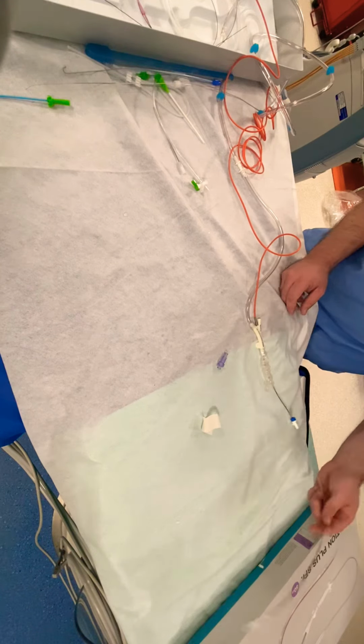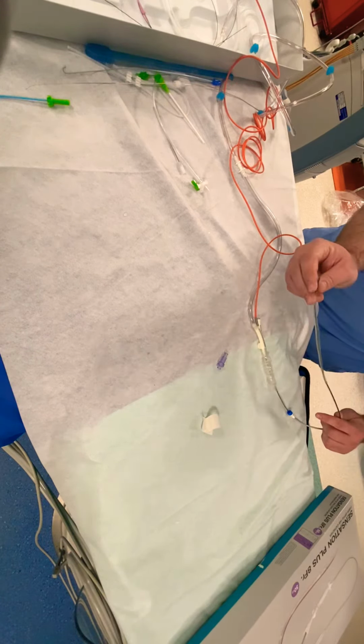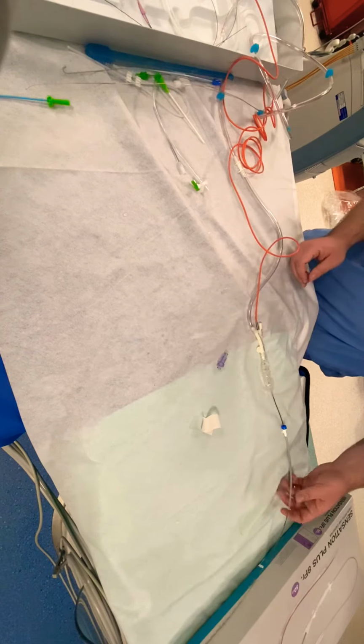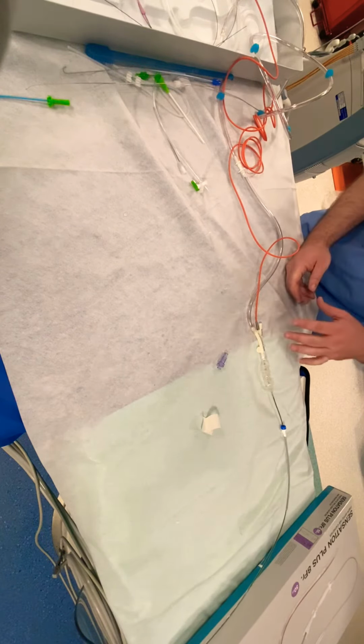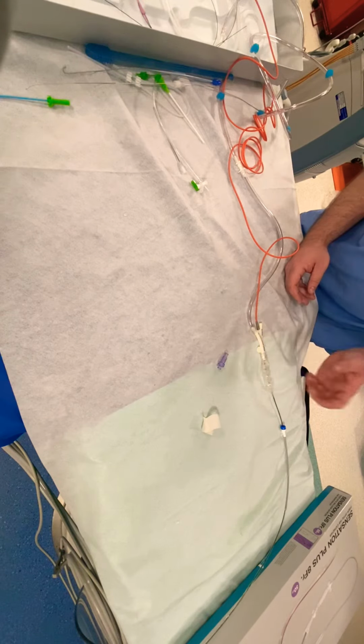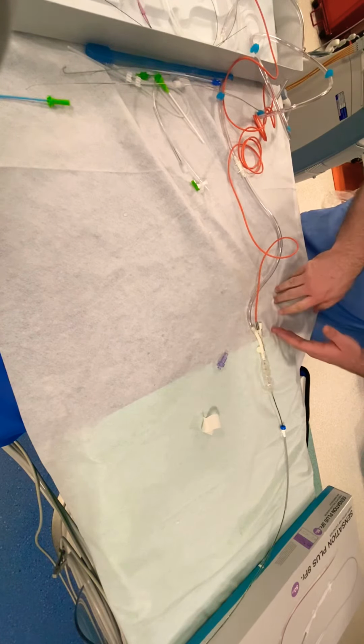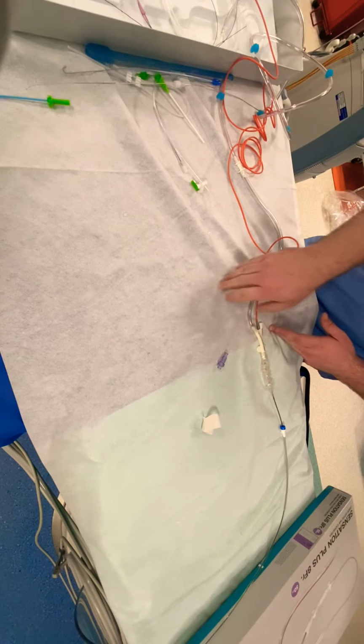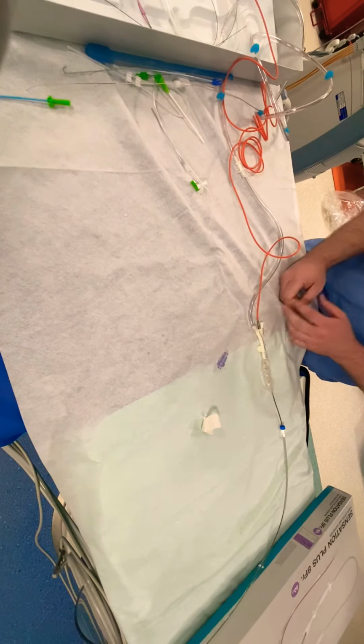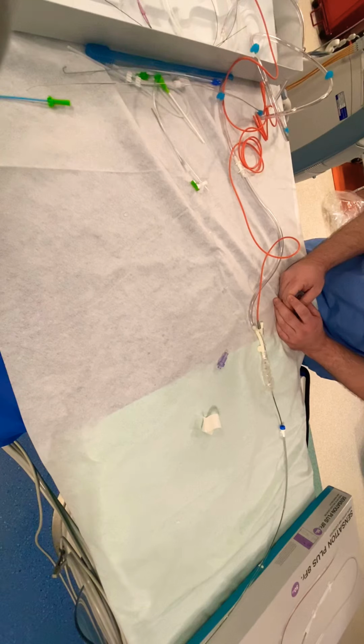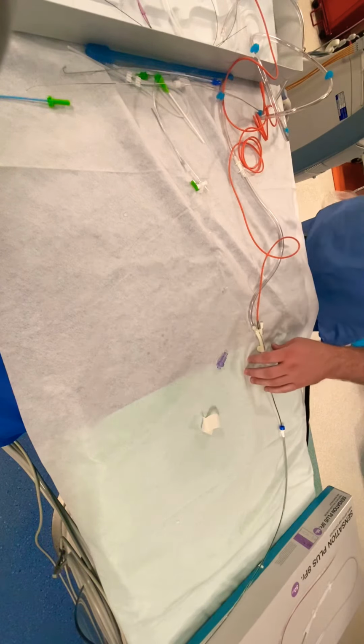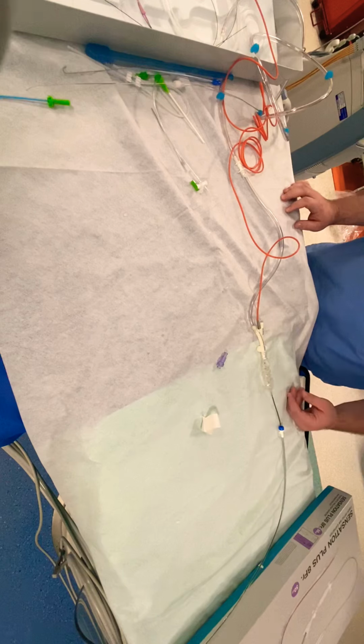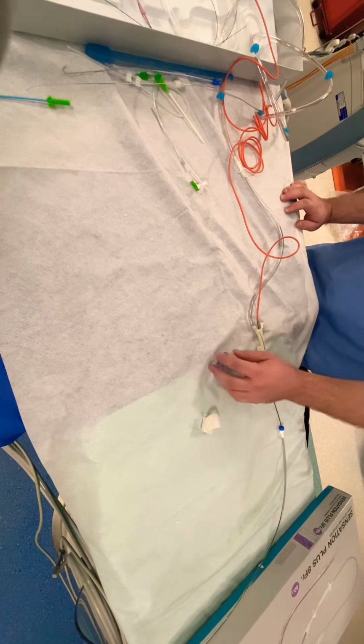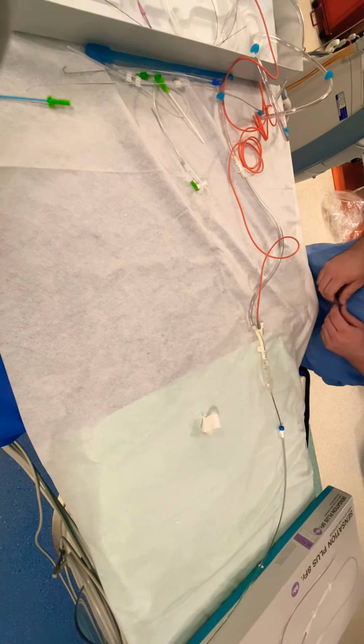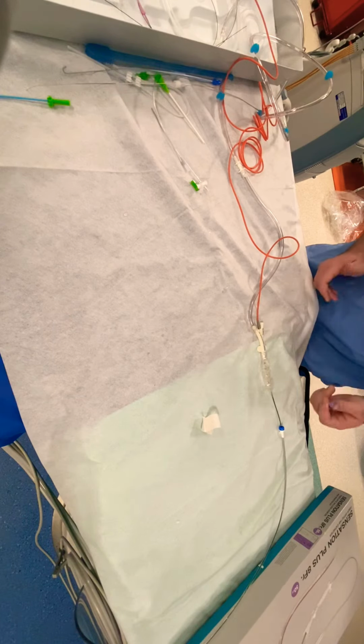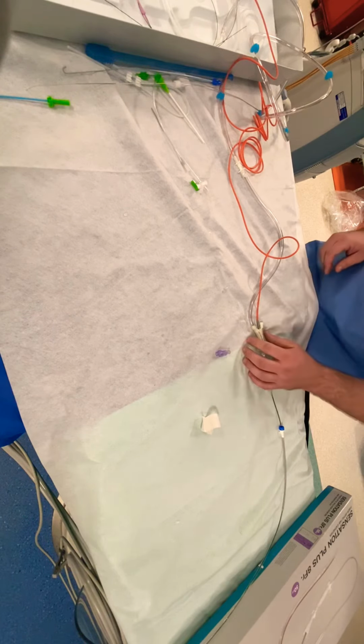At the very distal tip is where it gets its pressure, the fiber optic does, okay? So after it's done at zero in calibration, the balloon will auto-fill and deflate. It'll get its EKG rhythm, and then it will automatically go on every 1-to-1 is what it comes on in the automatic settings, okay? We need to leave ours in the most automatic settings that it has. We don't do balloon pump timing here. It is smarter than us. So thank you.